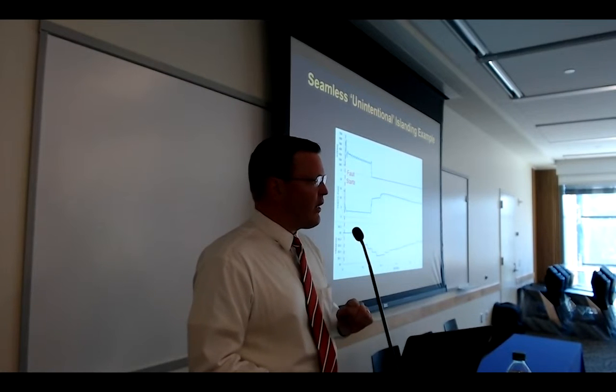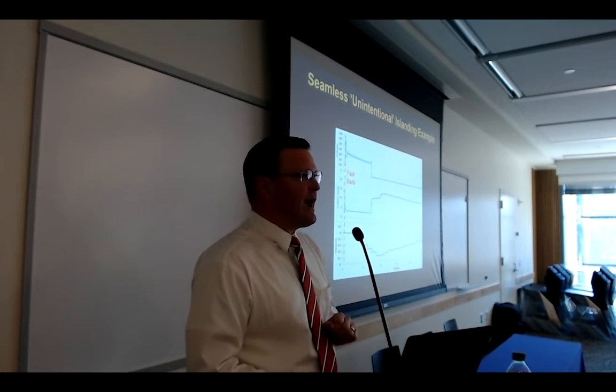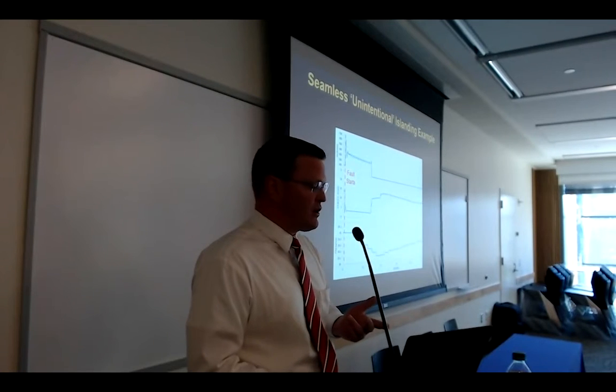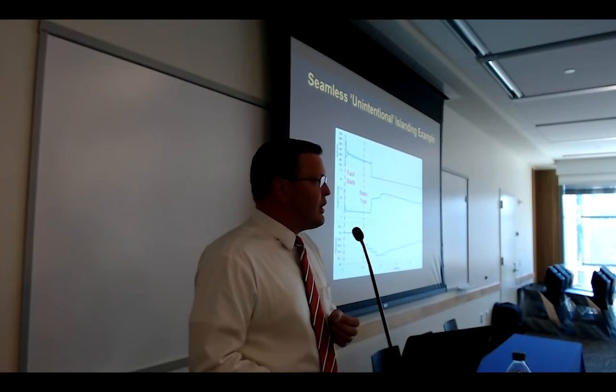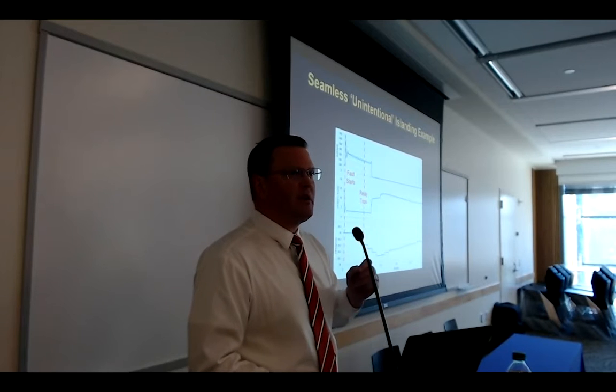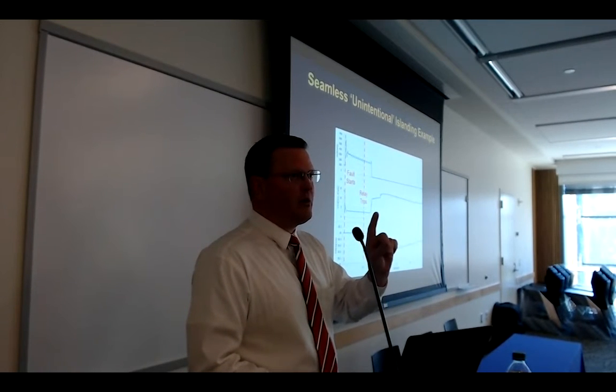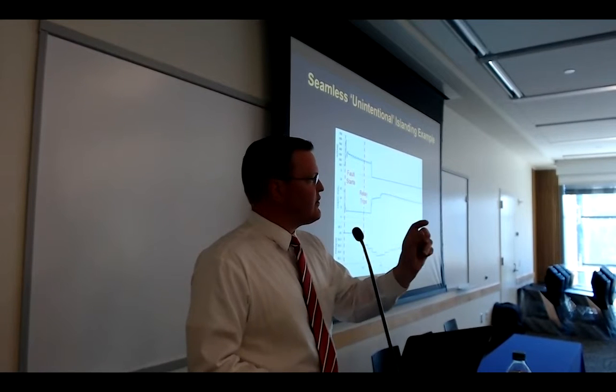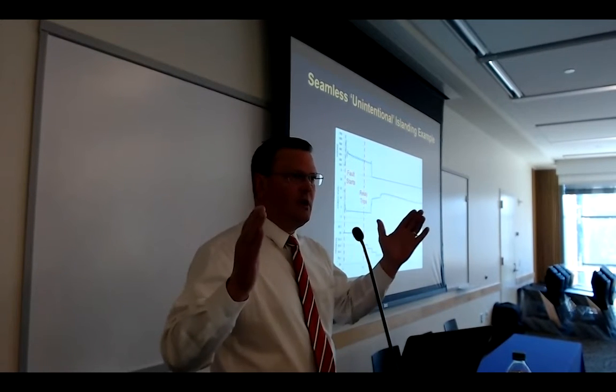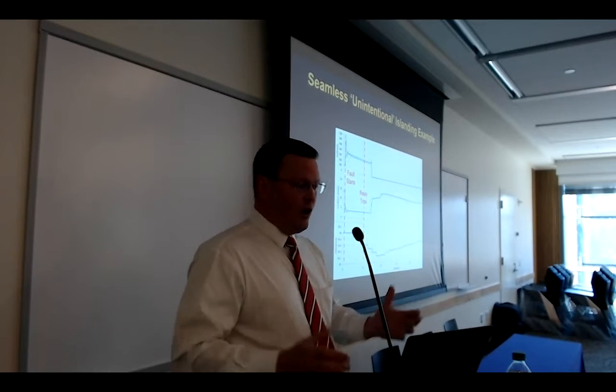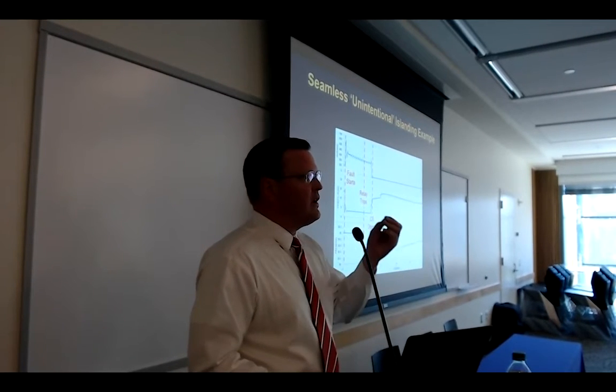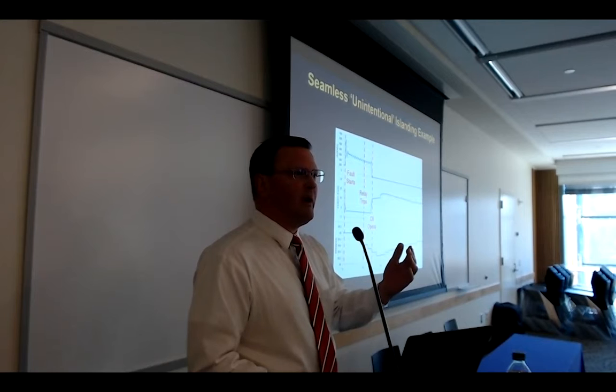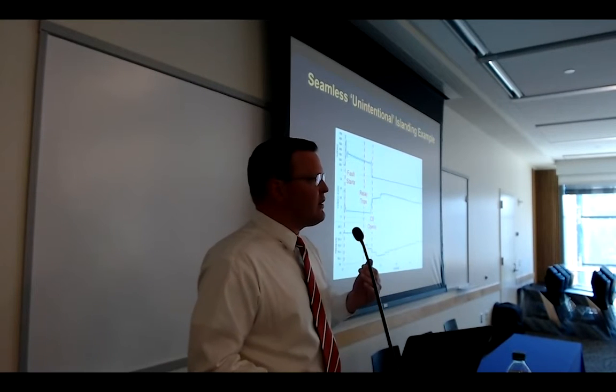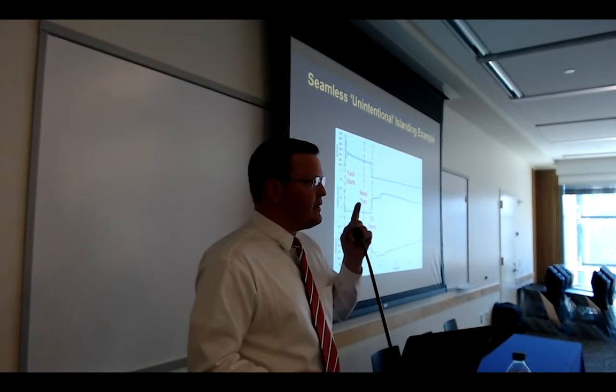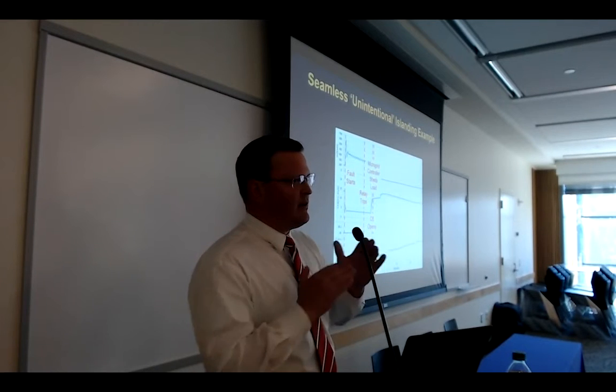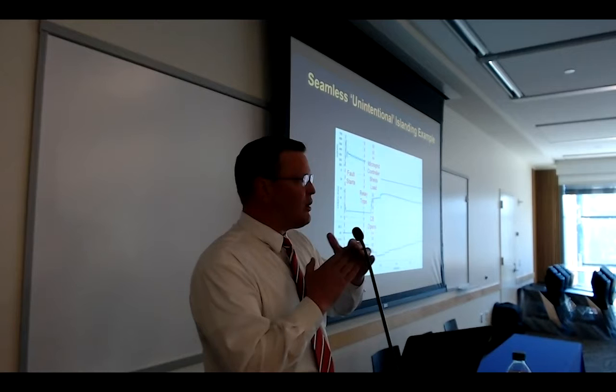What did the relay do in all this movement? The first thing is it saw that a fault occurred. The subtransient reactance was such that there was a significant burst of current. After some time, the protective relay said, wait, this is not okay, I'm going to trip. So it closed the contact, it excited a solenoid and a breaker, and that breaker began opening. It started extinguishing this current. At such point, the breaker opened, and look what happened. Now the voltage recovered on the microgrid, the current fell, and then a microgrid controller said, time out, you just had a topology change.